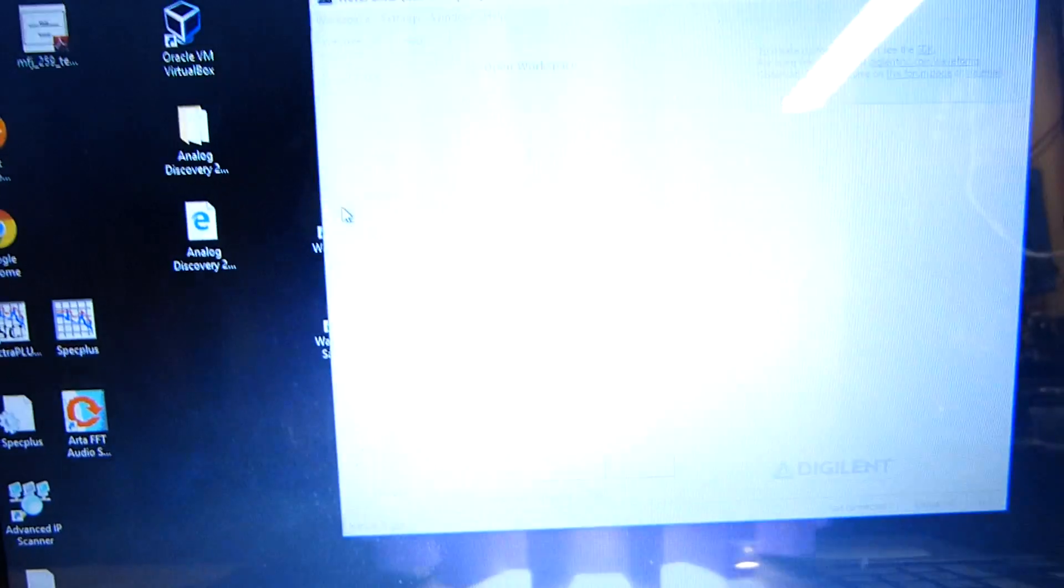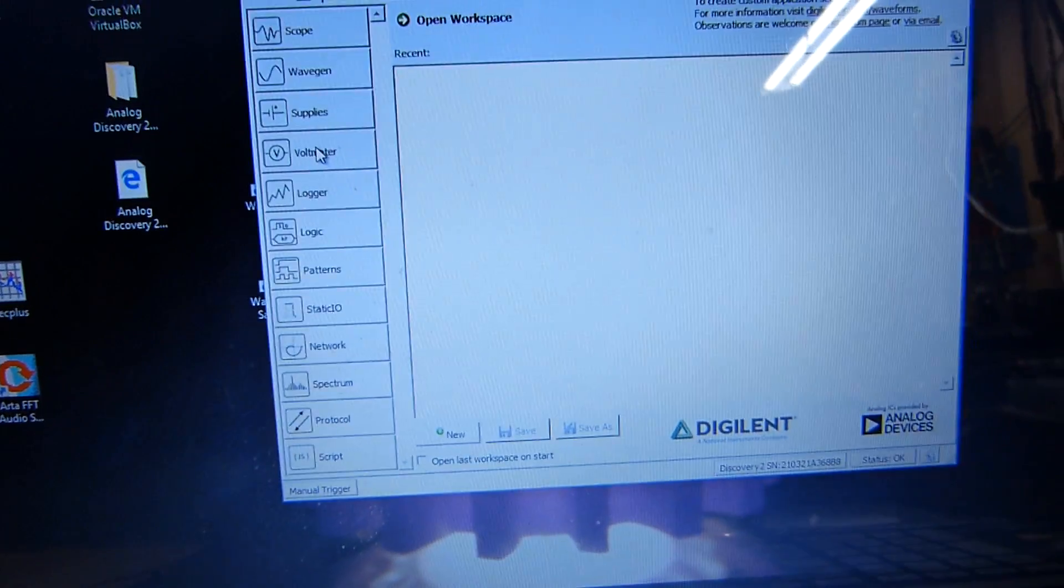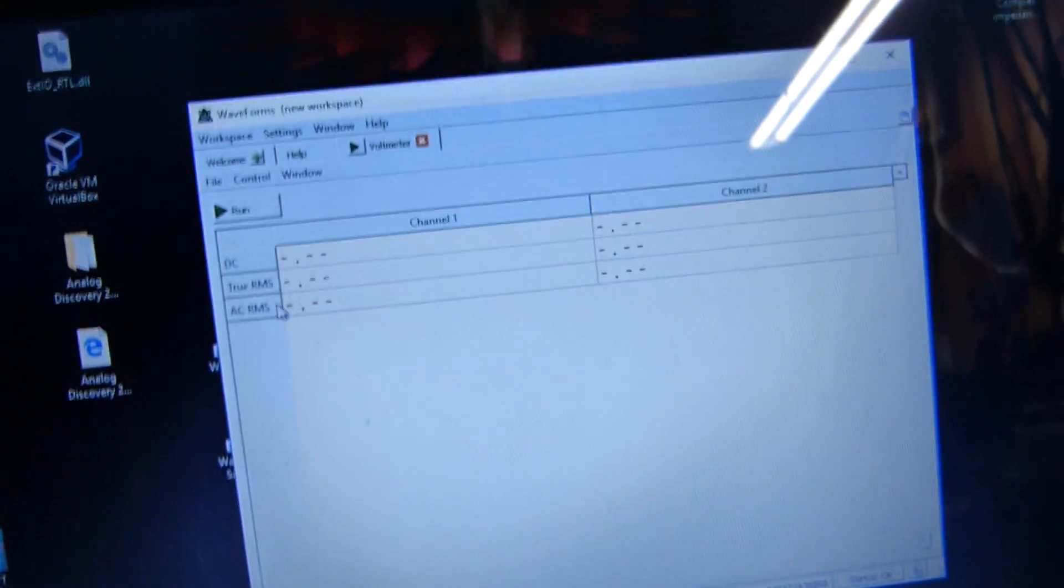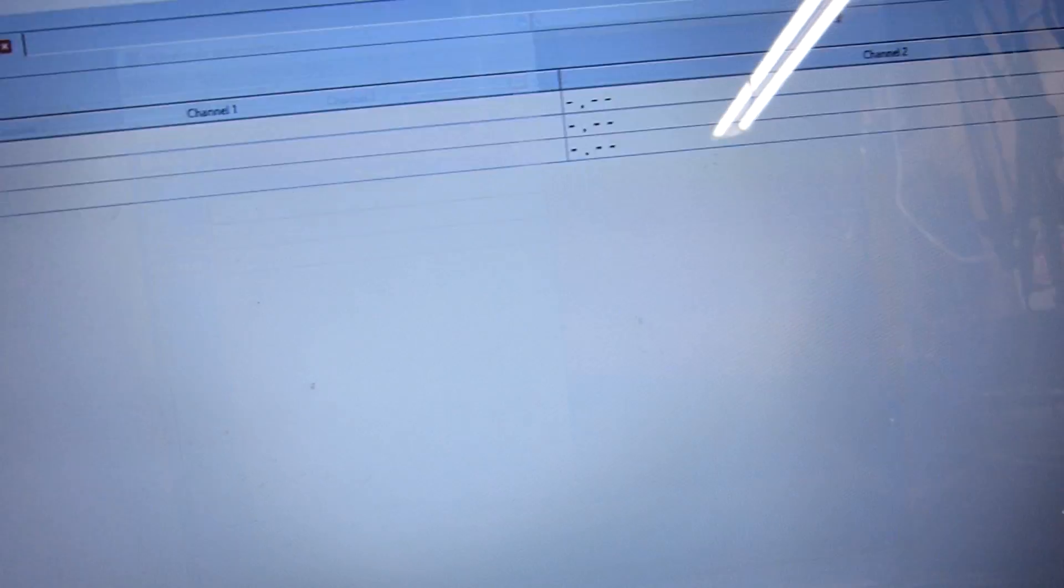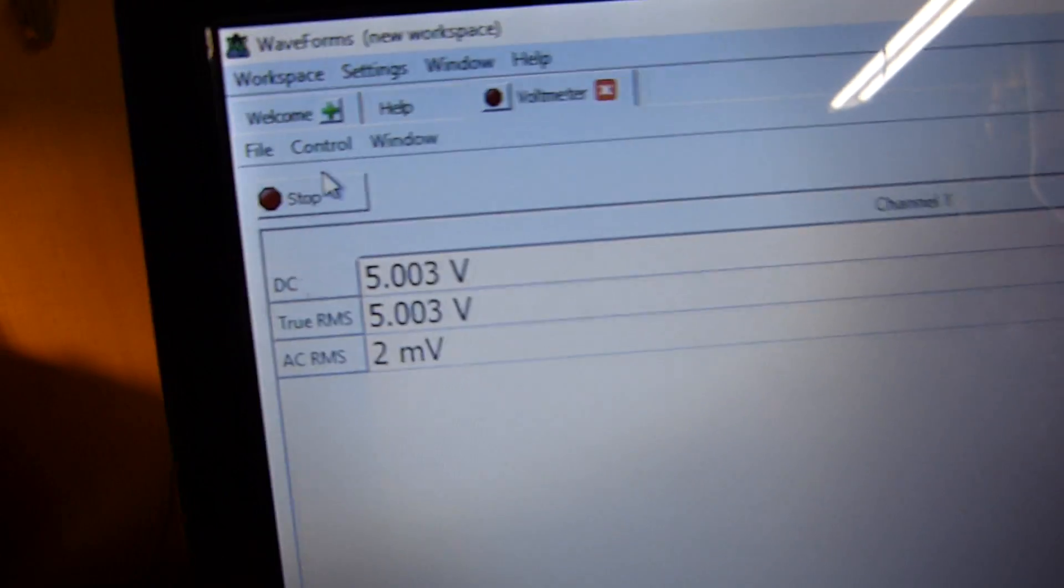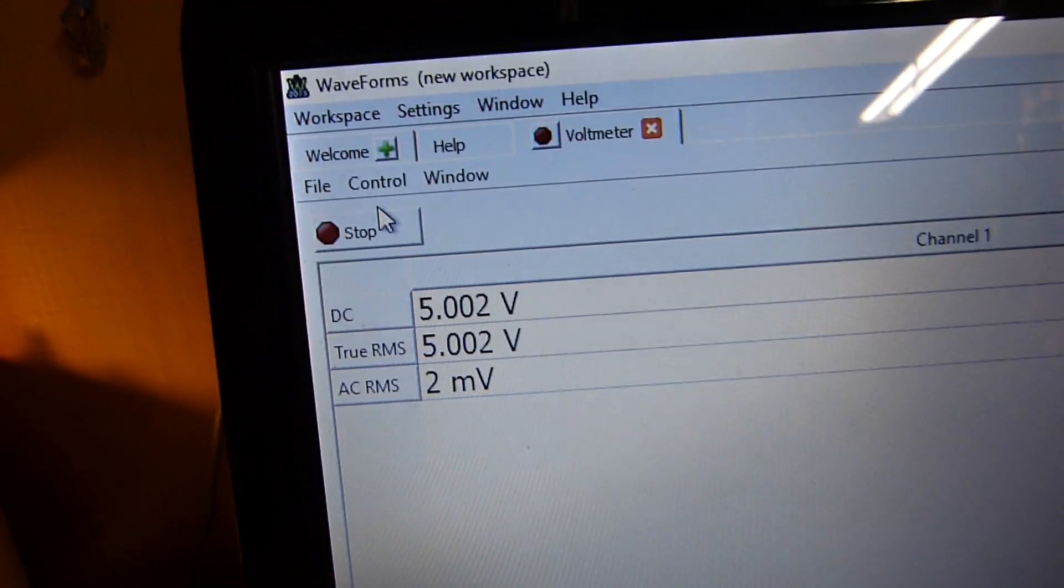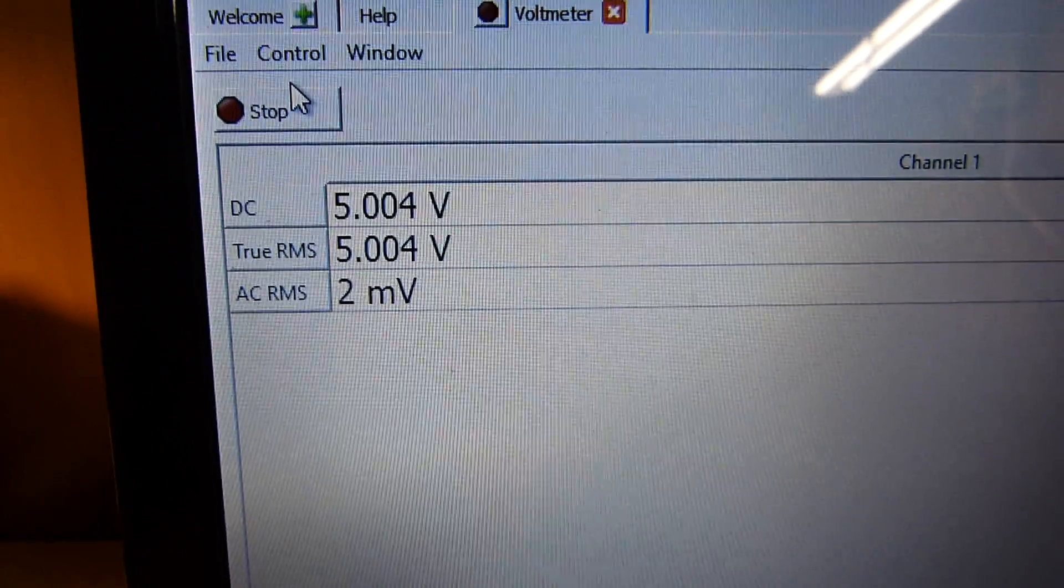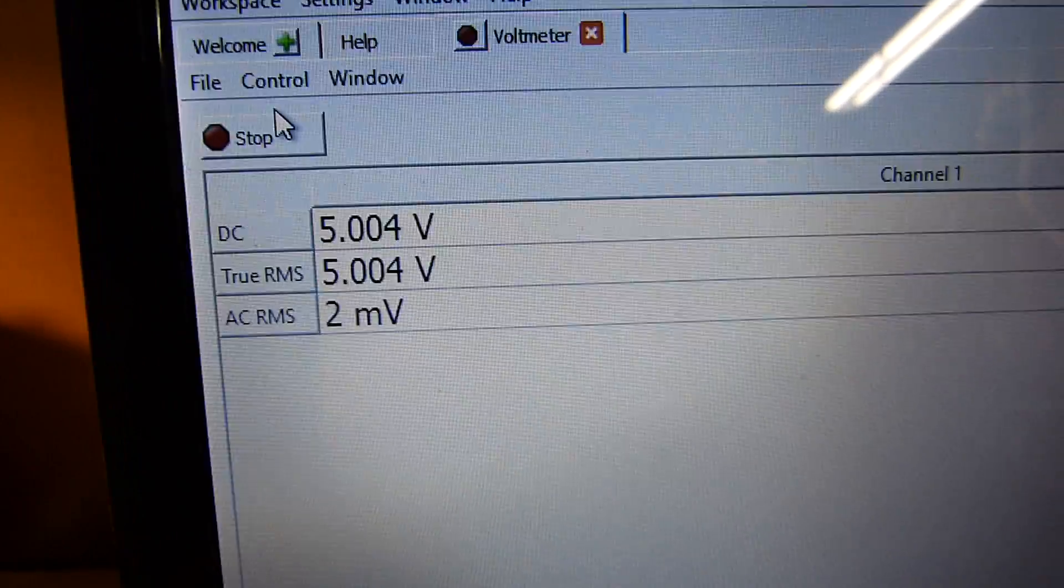By the way, I do have a skylight filter on the camera, hoping that helps the glare a little bit. Thanks for the suggestion. Let's open the voltmeter and say run. There it is, 5.003—it's smack on, and this calibrator is right too.